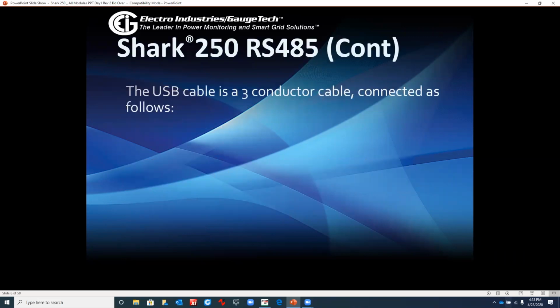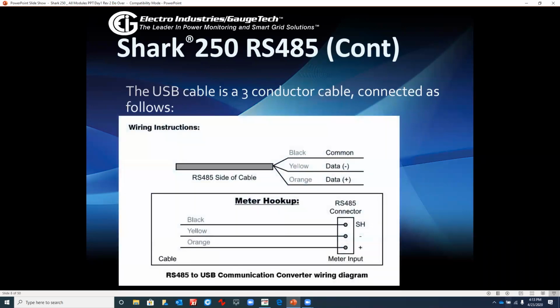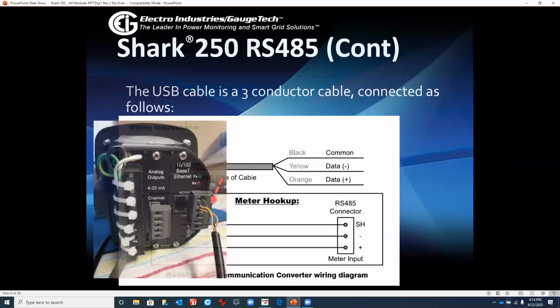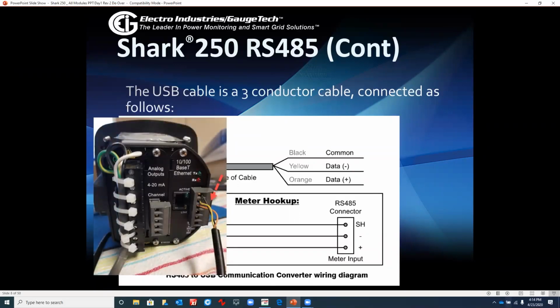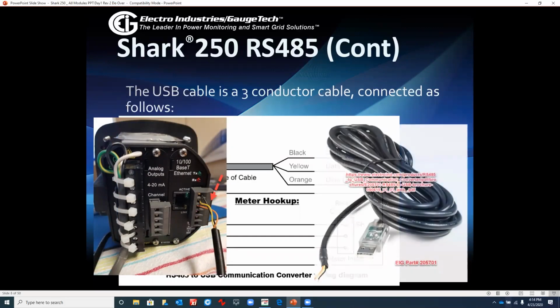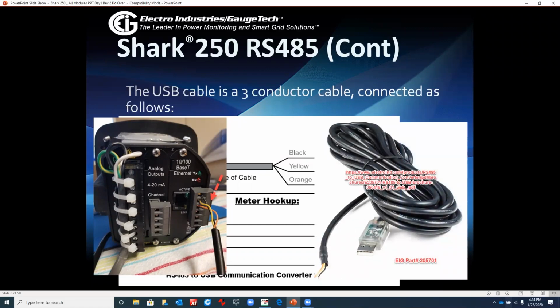So the USB cable is a 3-conductor cable, and it's connected as follows. You have the orange, which is a plus connection. So when you look at the wiring, you'll see orange, yellow, and black, and that's the side that will be connecting to the meter. Again, the orange is a plus connection, the yellow is a minus, and black is the shield. And this is what it would look like after you've made your connection to the back of the meter on the 485 port. And this is the cable that you would purchase online.